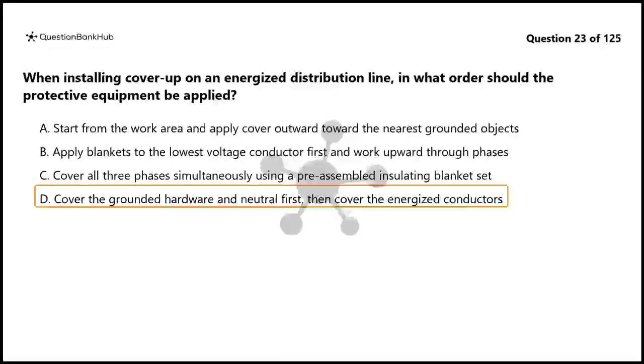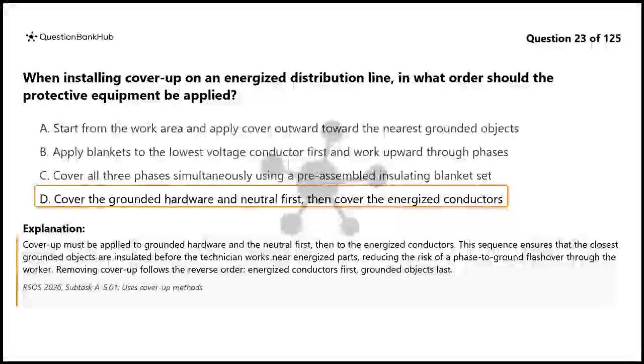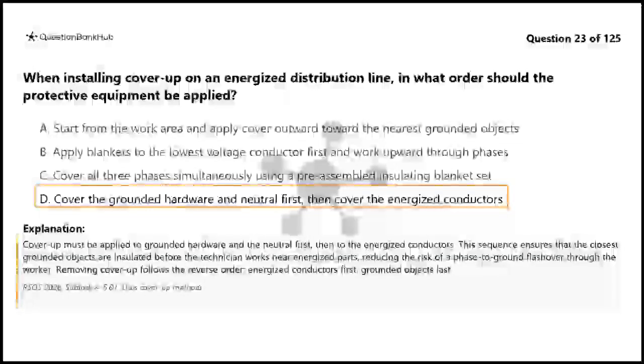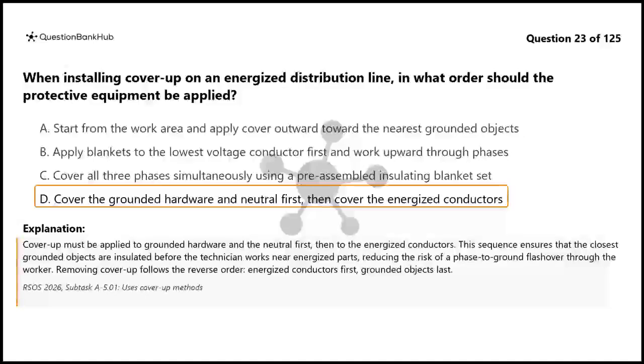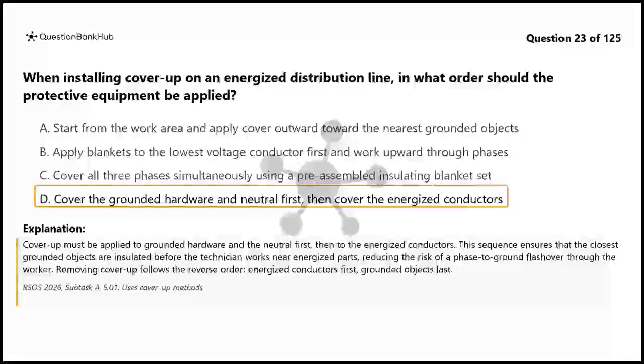The correct answer is D. Cover-up must be applied to grounded hardware and the neutral first, then to the energized conductors. This sequence ensures that the closest grounded objects are insulated before the technician works near energized parts, reducing the risk of a phase-to-ground flashover through the worker. Removing cover-up follows the reverse order: energized conductors first, grounded objects last.